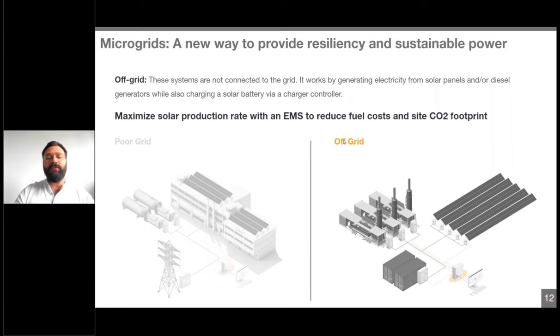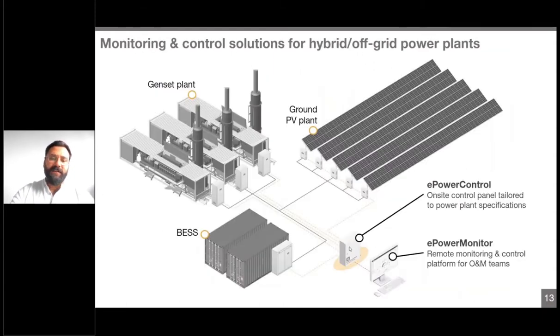Our controllers can also work in different applications or configurations, like the totally off-grid. As you can see here, there is no utility grid, and there is also a BESS that can be integrated. The main goal of our controller is to prioritize the penetration of renewable energies and to reduce the fuel consumption and the CO2 footprint. As I mentioned before, the controller will be connected to the PV and the gensets, but we can also integrate the PCS or the battery chargers in order to provide some specific strategies and comply with the requirements of each client. For sure, the controller will also have the monitoring system with all the KPIs retrieved from each equipment.